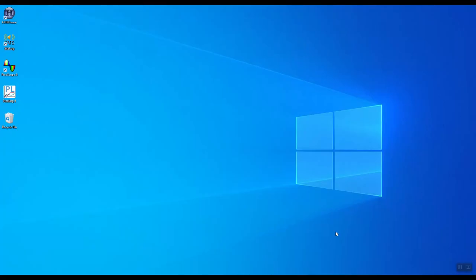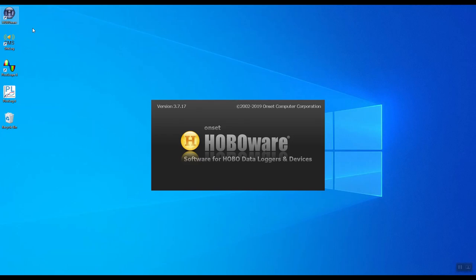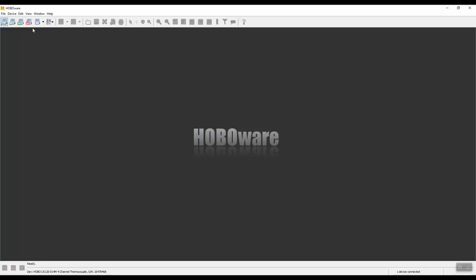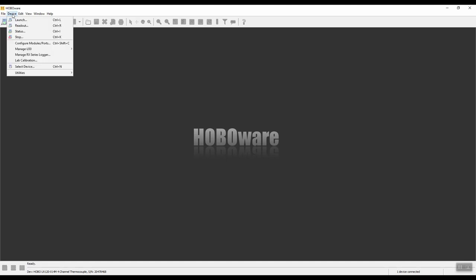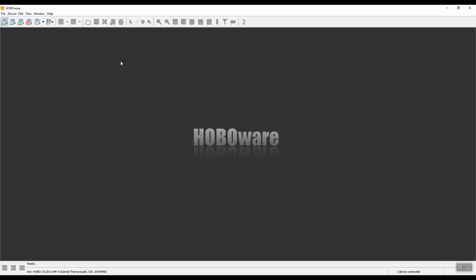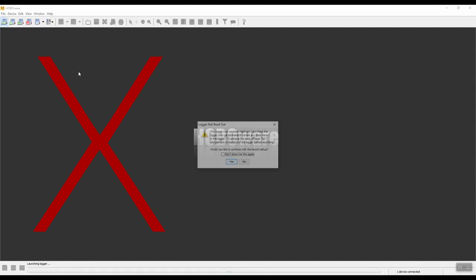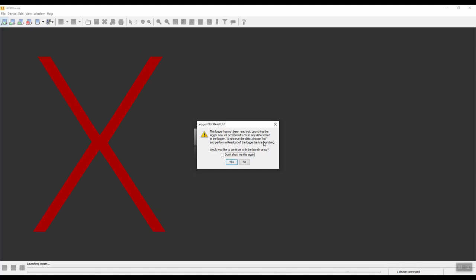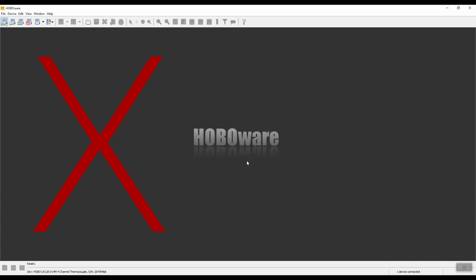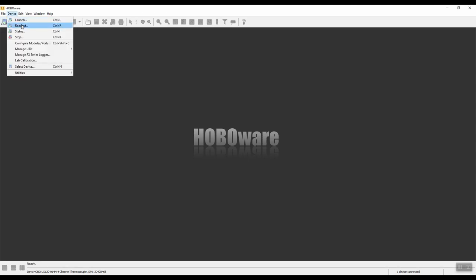To download the data from your Hobo data logger, simply connect the logger to your PC using the supplied USB mini B connector. Once this is done, click on the HoboWare software. The first thing you need to do is go to device and then readout, or select the second button. Do not click on launch device as this will erase the data from your data logger. You'll get a message saying logger not read out, launching the logger will erase the data stored in the logger. Click on no.